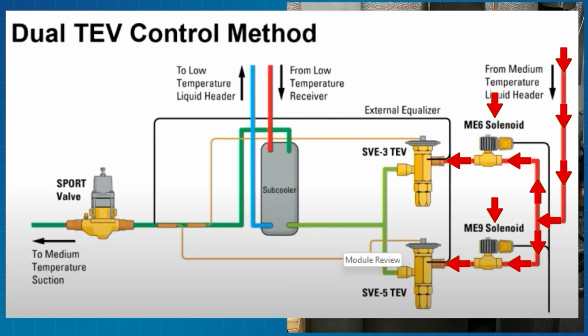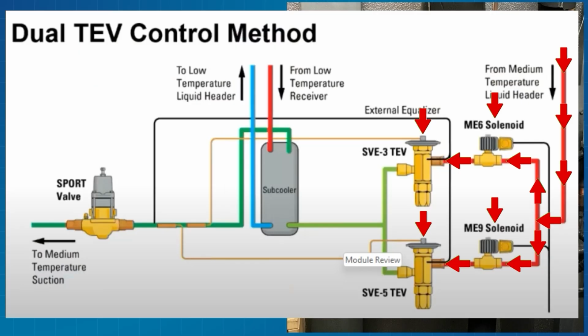It's gonna feed 2 TXVs, they're gonna be different sizes, one's small, one's big. They're gonna be labeled that way, large and small, however. They're not gonna be dramatically different, but you'll see a 3 and a 5, you'll see a 5 and a 10 on some of the big boys. That TXV is gonna feed my evaporator, which is my primary side of my subcooler, and I'm gonna come out the suction, here's my EPR, and then I'm going to the suction.